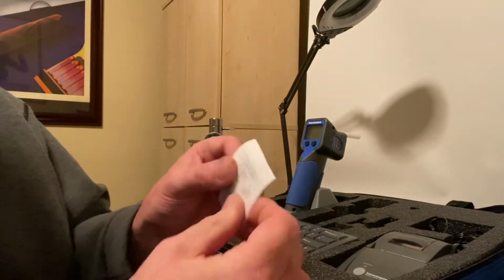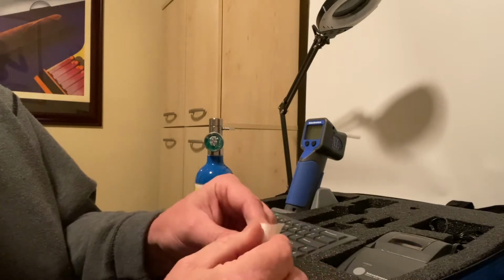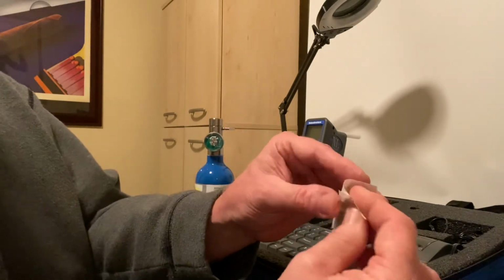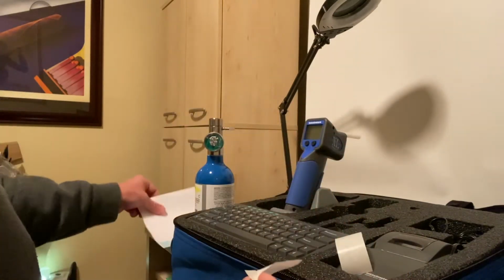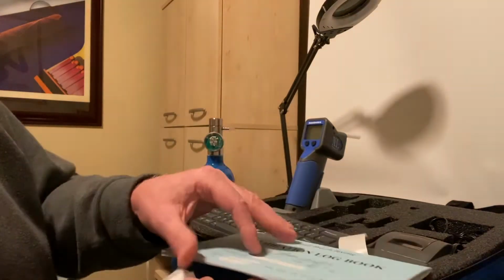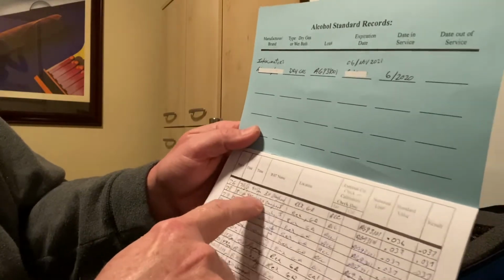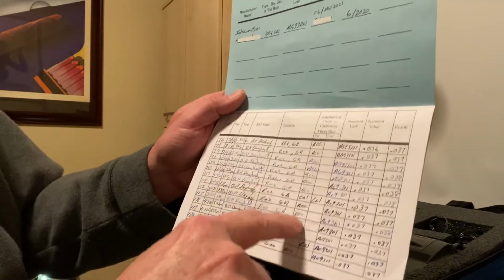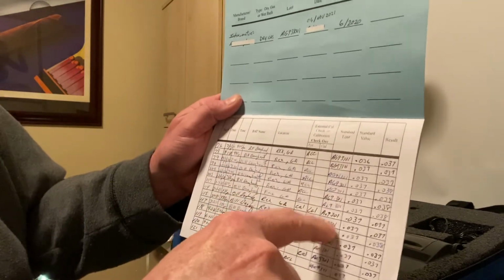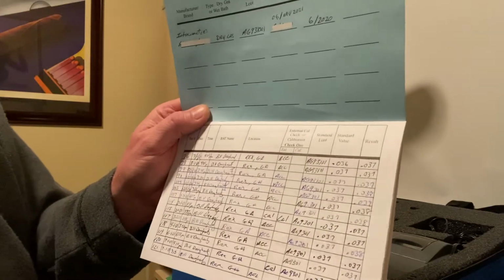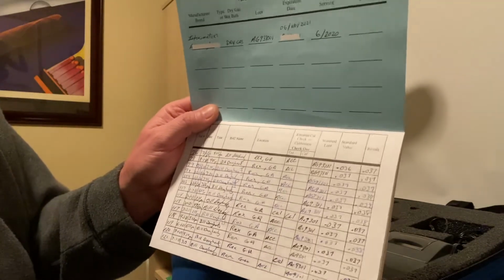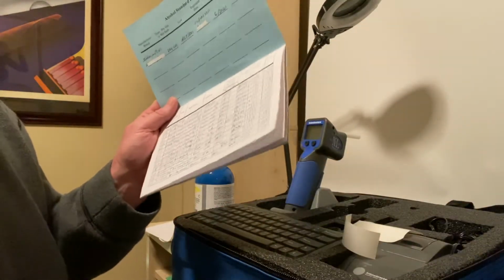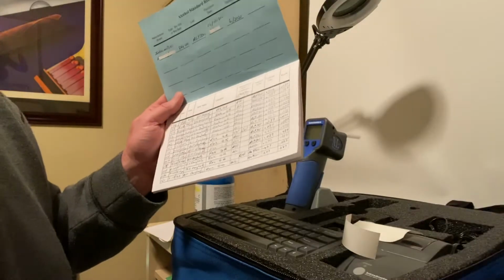Now this, I would take this, and I think I've got another roll in here of the double-sided tape. I would take this and peel it off and enter this information into my logbook. All I'm doing is the test number, the date that I took it, my name, where I was, that I did an accuracy check, then the lot number of the tank, and where my ranges fell. I've never had any problems with this machine not being in the correct accuracy range. If it's out of range, again, everything is going to be in this manual, and I'm also going to include the training book that I was given for my classroom training.